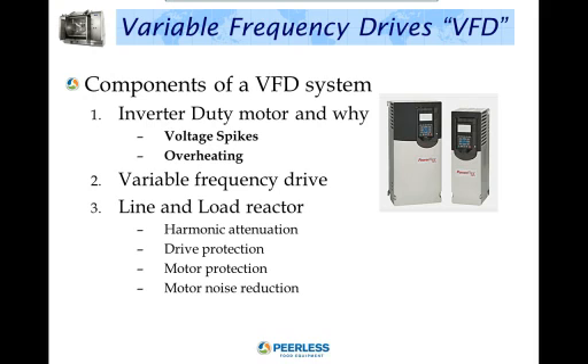On the line side, reactors stabilize the current waveform with reduced harmonic distortion and reduce the burden on upstream electrical equipment by absorbing line spikes and filling some sags that can prevent overvoltage and undervoltage tripping problems. For example, when the utility switches power factor correction capacitors on the electrical power grid, it creates voltage spikes. The impedance of the reactor in the input circuit helps prevent these voltage spikes and virtually eliminates nuisance tripping of drives due to overvoltage.